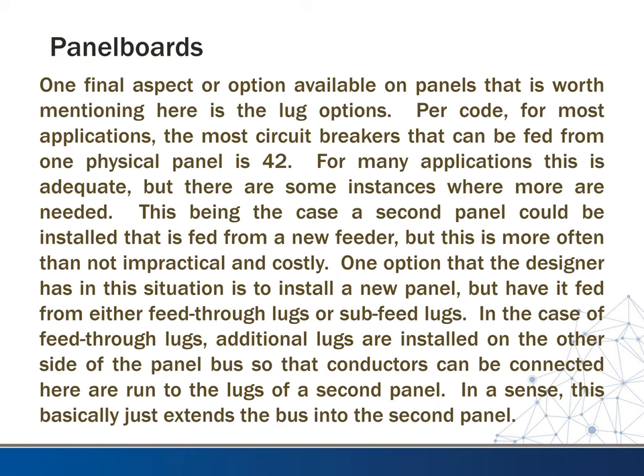One final aspect or option available on panels that is worth mentioning here is the lug options. Per code, for most applications, the most circuit breakers that can be fed from one physical panel is 42. For mechanical panels, this can be larger, but for many applications, this is adequate, but there are some instances where more are needed. This being the case, a second panel could be installed that is fed from a new feeder, but this is more often than not impractical and costly.